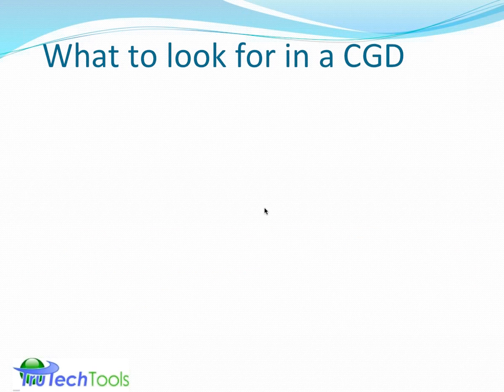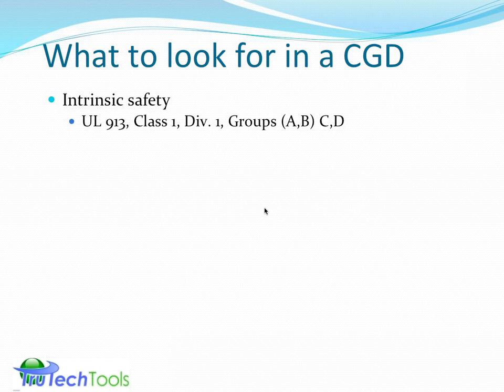Okay, so what are you looking for in a combustible gas detector if you want to comply with this BPI 1200 standard the way it exists right now? We'll just go back and pretty much recap. We're talking about intrinsic safety as it's written right now. That boils down to looking for a product that has the UL 913 rating for Class 1 Division 1, Group C and D at a minimum, but it could also be A, B, C, and D. That means the type of gas, the type of environment, and it's a standard written by Underwriters Laboratories, UL 913. If you see this mark on the equipment, then you would be in compliance with the intrinsic safety concept of the BPI 1200 standard.